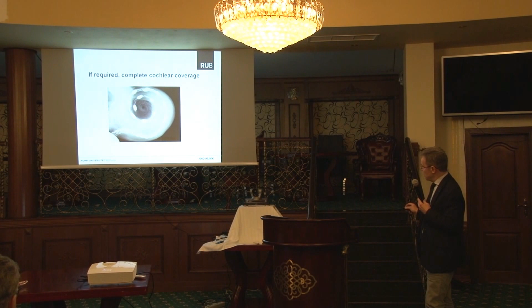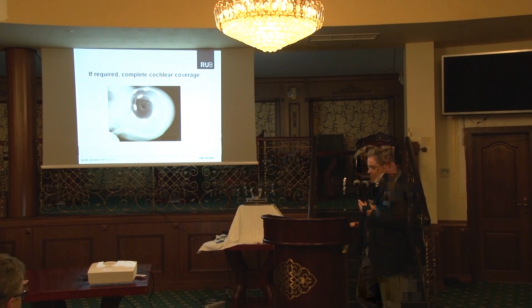This picture shows you the result of a study of measuring the cochlear duct. And what we find is this Gauss curve, which shows that the cochlear duct, or the length of the cochlea, varies between 25 and 36 millimeters. So it's maybe not advisable to take the same electrode length in every patient, but look for the cochlear length and then adapt the size of the electrode. If required, we prefer complete cochlear coverage, so this electrode really goes into the tip of the cochlea where the low frequencies are located and the neural elements can be stimulated in this way.